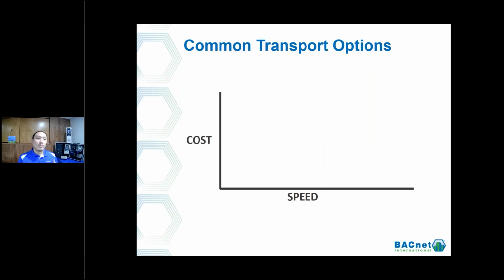Now we're taking one more step back, looking at how that data is transmitted, the physical portion of it. There are two main BACnet implementations or physical mediums being used right now. The lowest cost, and the slowest at this moment, is MSTP, which is more of an RS-485 based network. Its limitations are based off of what you can do on RS-485, but it's also one of the least costly.